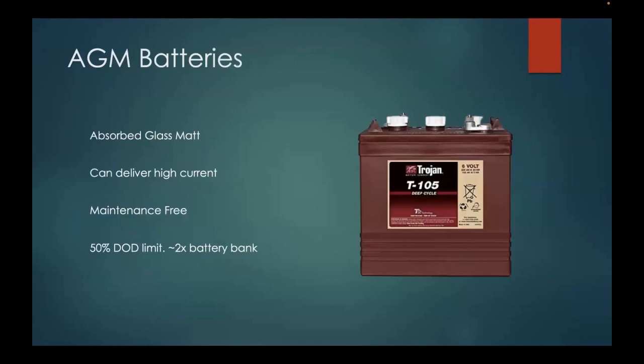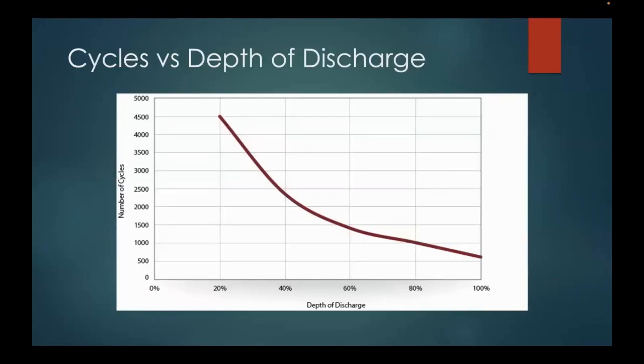Now let's take a look at this. Renvu sells this battery. This is a cycle versus depth of discharge chart that's on the battery spec sheet. You will not find this for lithium ion batteries, and I'll tell you why in a minute. So if we look at the 50% area, you can see the deeper you discharge these batteries, the fewer cycles you get. Now, what we're looking at here is depth of discharge, or how much energy you've used in the battery — that's depth of discharge.